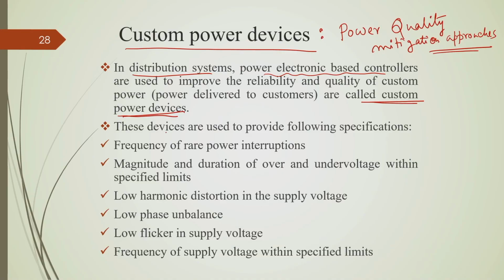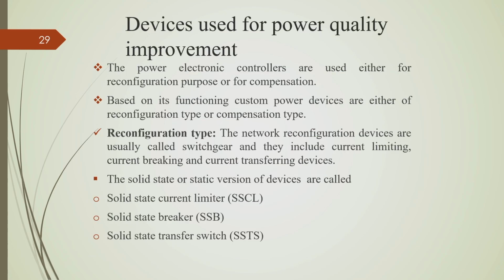Okay. And these devices are used to provide the following specification, frequency of rare power interruptions, magnitude and duration, due to over voltage and under voltage. That means, if they are used for over voltage and under voltage mitigation, they have a frequency which is similar to the supply frequency. They are used to mitigate harmonic distortion, voltage unbalance or voltage imbalance, and to mitigate voltage flicker. Okay. For this purpose we use them, and there are two types of custom power devices. One is called the reconfiguration type, which is used to reconfigure the network, for current limiting, circuit breaking and current transferring.